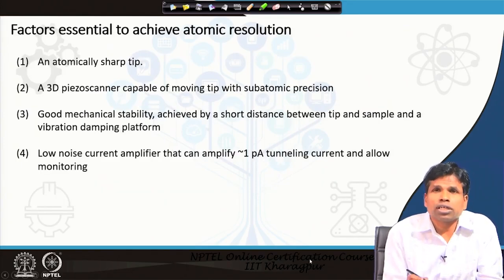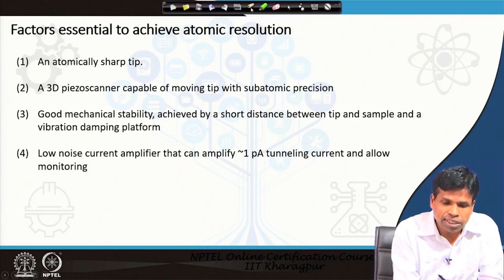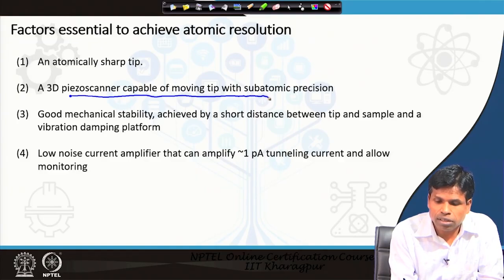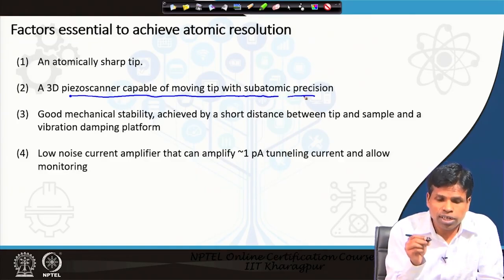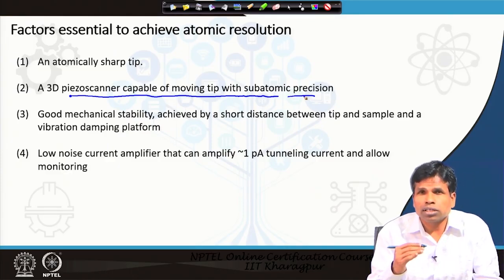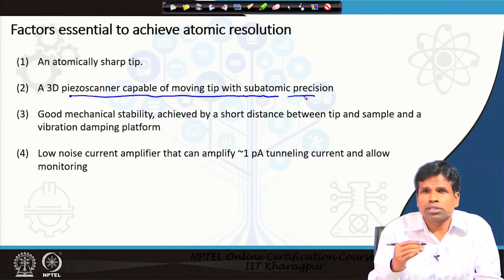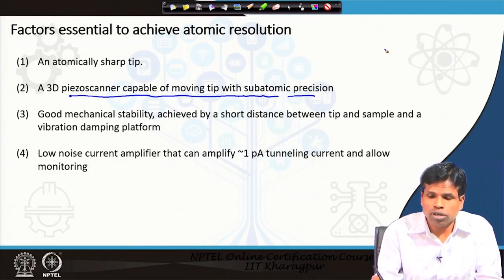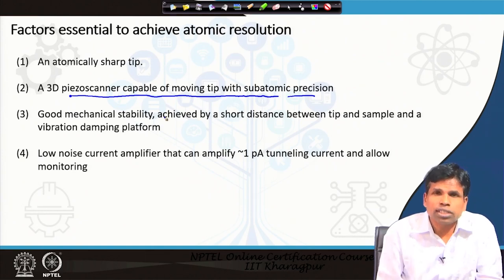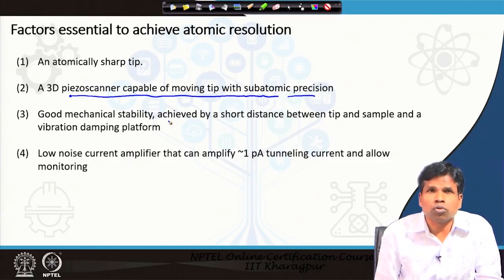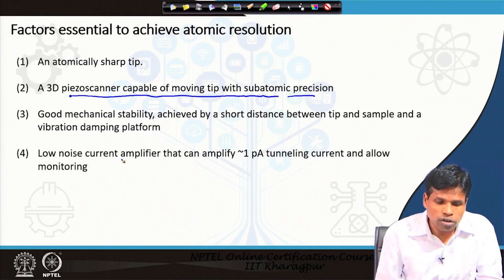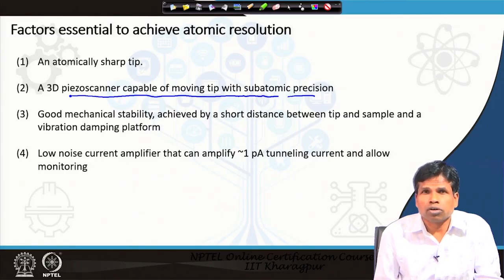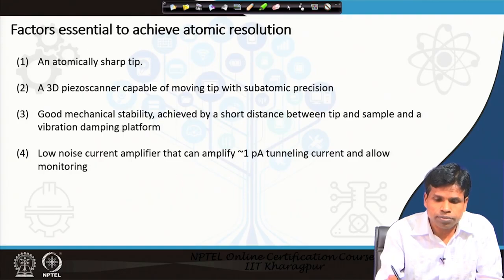To achieve atomic resolution, the factors required are: an atomically sharp tip, and a 3D piezo scanner moving the tip and sample with atomic precision. A piezoelectric scanner is used to move the tip at very small steps at the angstrom level, so we can accurately measure how much the tip has gone up or down and accordingly create the surface topology of the sample. Good mechanical stability is required because the tip-sample distance is very small, along with a vibration damping platform and a low-noise current amplifier that can amplify pico-ampere tunneling current.